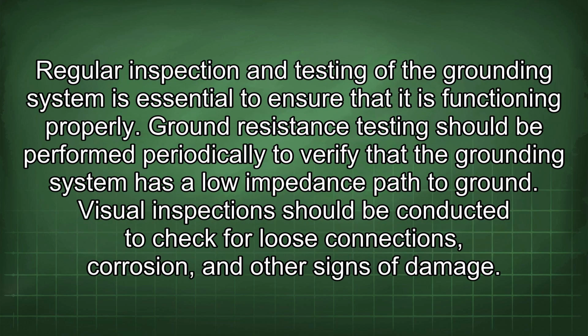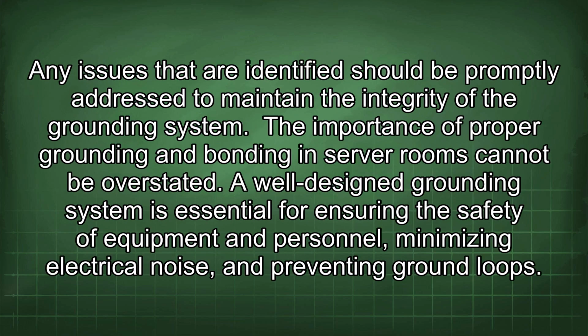Regular inspection and testing of the grounding system is essential to ensure that it is functioning properly. Ground resistance testing should be performed periodically to verify that the grounding system has a low impedance path to ground. Visual inspections should be conducted to check for loose connections, corrosion, and other signs of damage. Any issues that are identified should be promptly addressed to maintain the integrity of the grounding system.